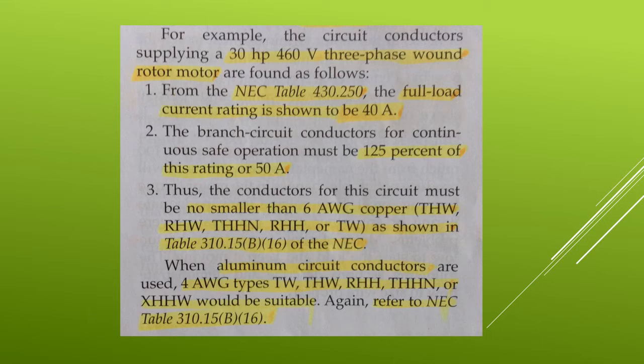For most AC installations, the ampacity requirement of a motor is 125% of the motor's full load current rating. Again, for most AC motor installations, the ampacity requirement of a motor is 125% of the motor's full load current rating. The nameplate should show the full load current rating, but if it does not, refer to table 430.250 of the NEC.